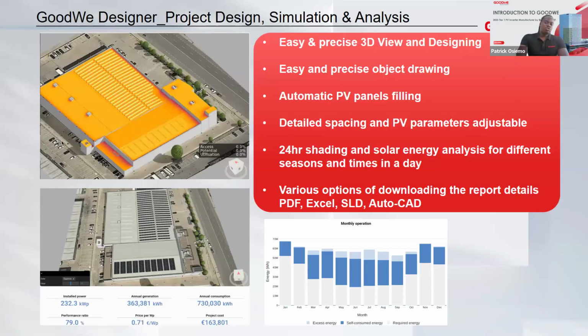So how it looks like, this is what you can achieve using the GoodWe Designer. Get 3D, automatically lay out your panels, choose which spacing to use and the orientation, check on your insulation, and automatically fill in your panels on the roof. Not just roof, you can also do ground mounted systems. And it will give you cost analysis. It will also give you an SLD of your system. It will also size for you the cables on the DC and on the AC side, and also size the breakers on the AC side automatically.